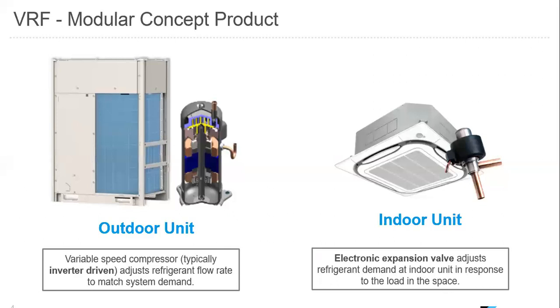We can modulate from 10 up to 100%. And at 100%, we're actually spinning faster than 60 hertz, and so that allows us to have a lot of head pressure and low temperature applications. And then our indoor units, we're variable at the indoor unit as well. We have an electronic expansion valve, and that expansion device is going to open and close. It's going to modulate hundreds of steps of incremental capacity potential inside of it. So we can actually provide the right amount of refrigerant flow across that coil at any given time.